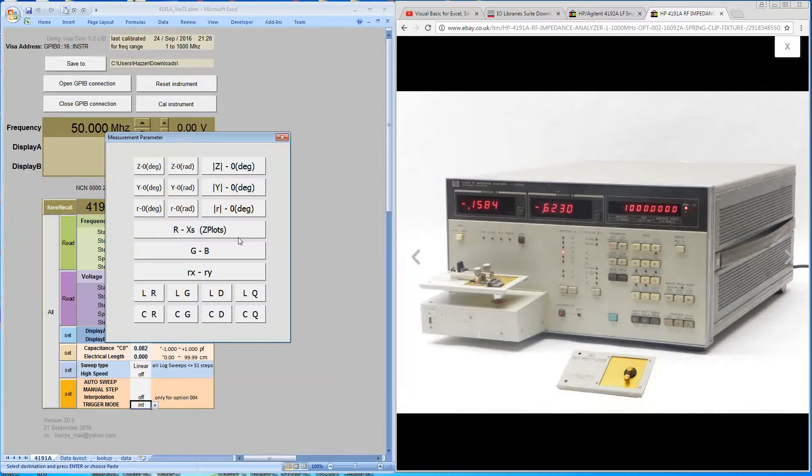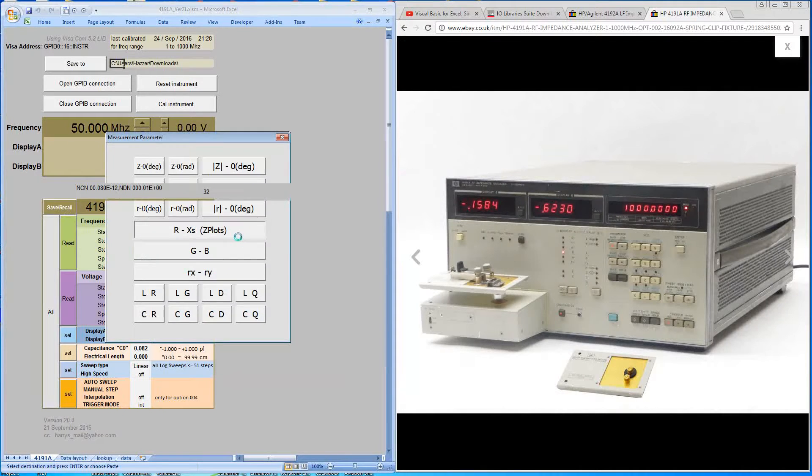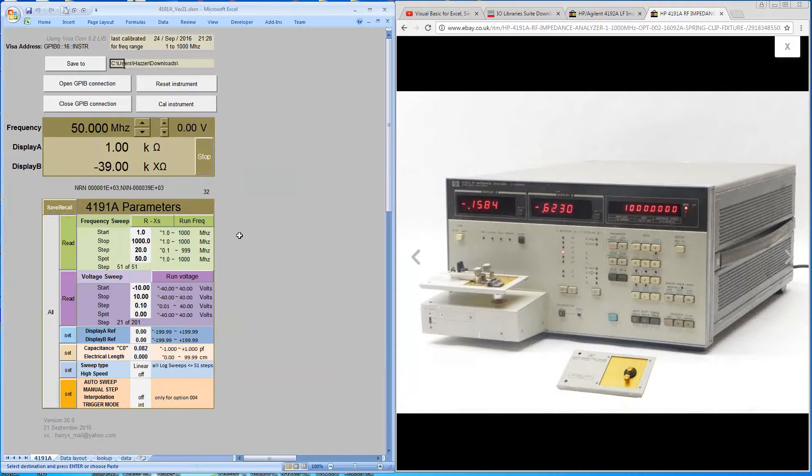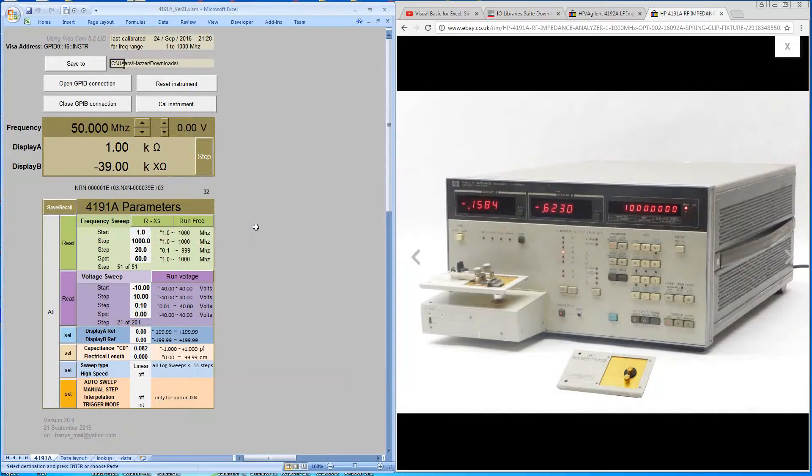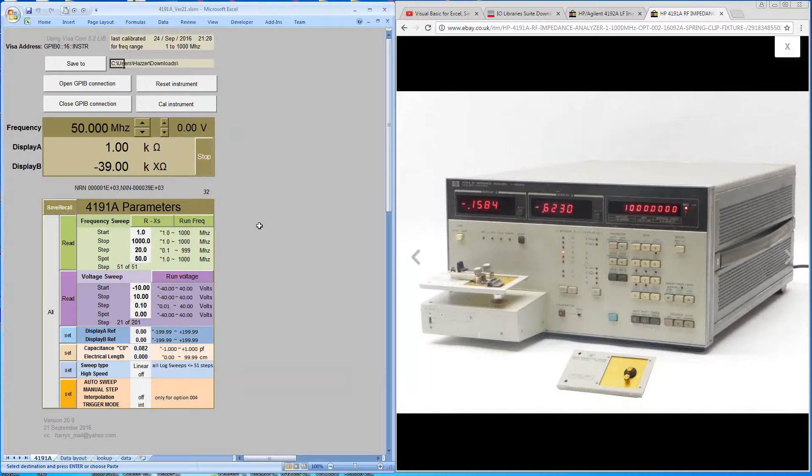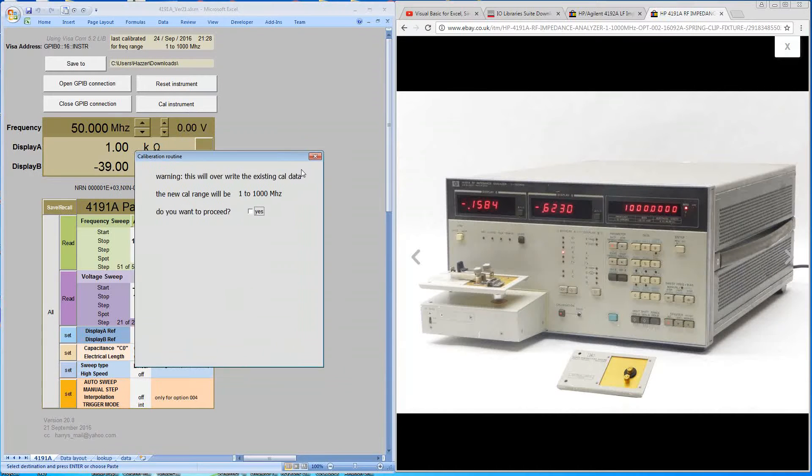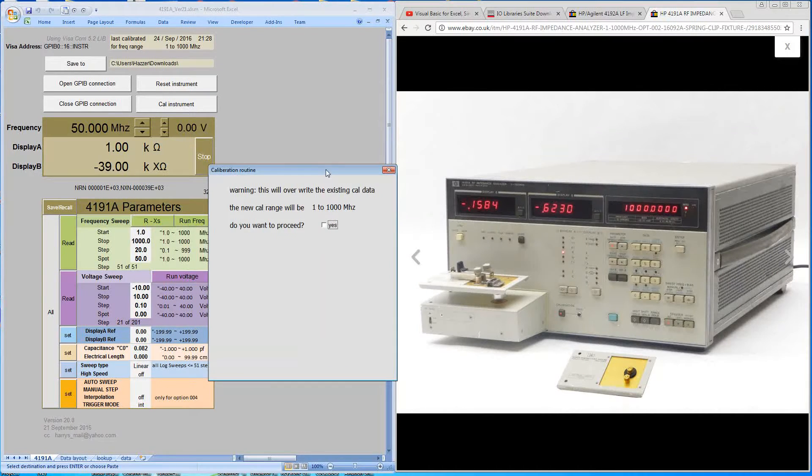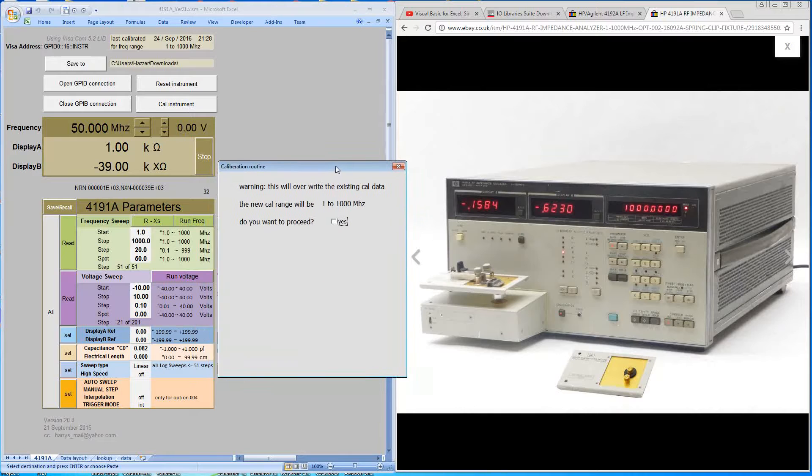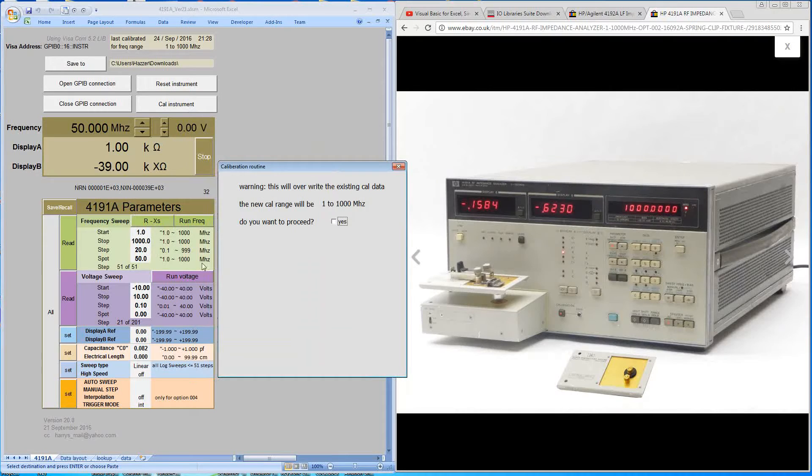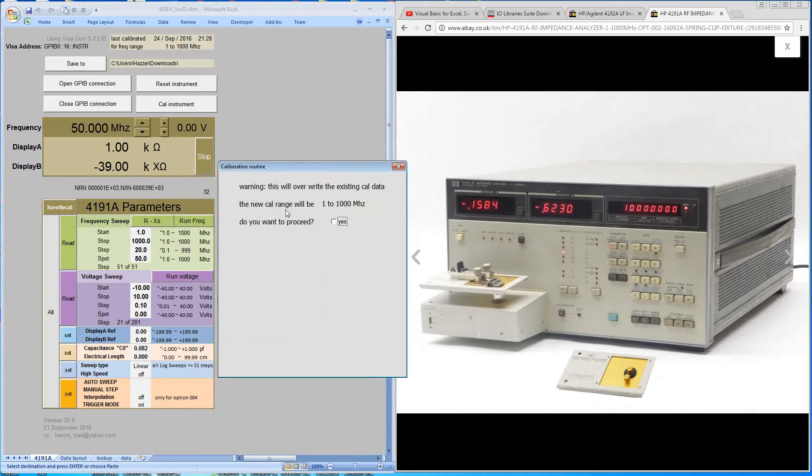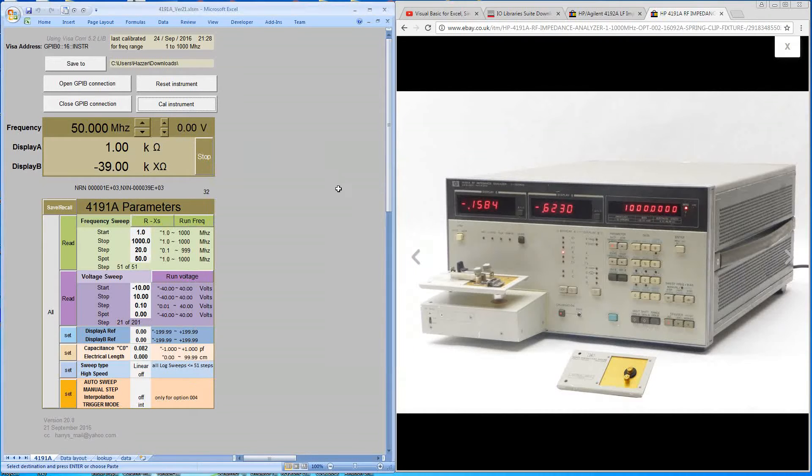OK, so the other thing you need to do is you need to calibrate the machine. Now I'll actually cover this in more detail in the next video. But just to briefly say that the 4191A can retain one set of calibration data. So every time you change the frequency range, if it's outside the calibration range, you'll need to do a new calibration. And it's just warning you that it's going to overwrite the existing CAL data. And do you want to proceed? OK, so more on that in the next video. But that's a brief introduction to the user interface.